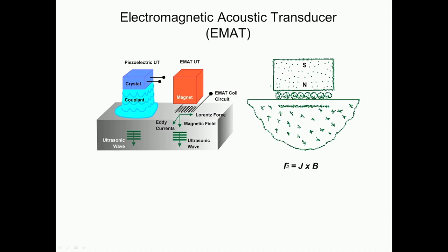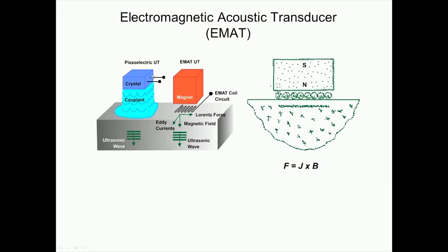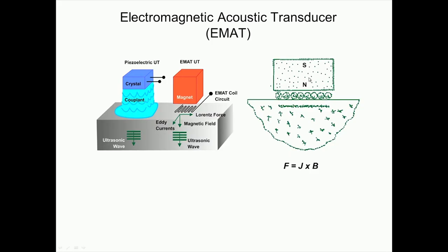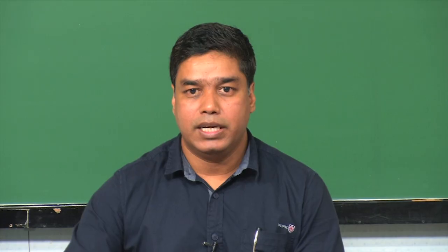So, this is the mechanical force which will generate the ultrasonic vibrations. In this case, unlike the piezoelectric units, the mechanical vibrations or the ultrasonic waves are generated in the sample itself due to the interaction of the induced current and an external magnetic field, which is very different from the piezoelectric units, where you need a pulse generator, some electrical signal being sent to this unit and so on. In this case, the vibrations, the waves are directly generated into the sample, and that is why you do not really need to make that contact with the sample, and therefore, you do not need any couplant in this case.